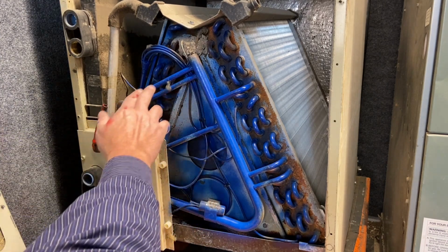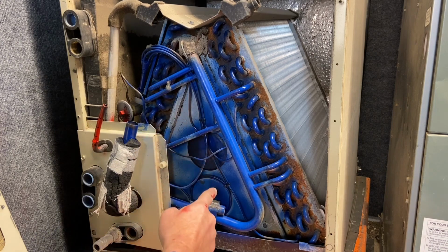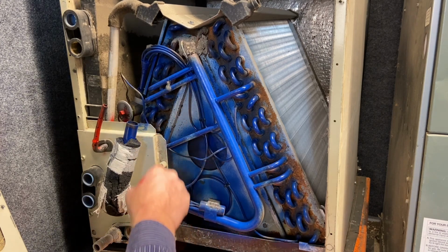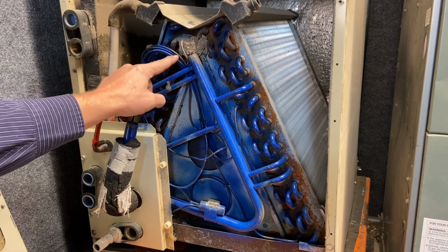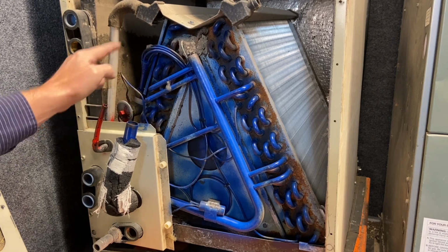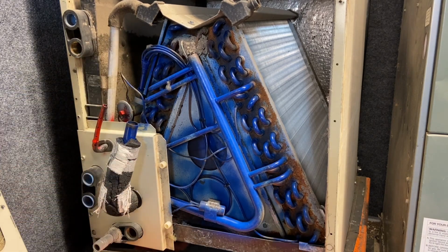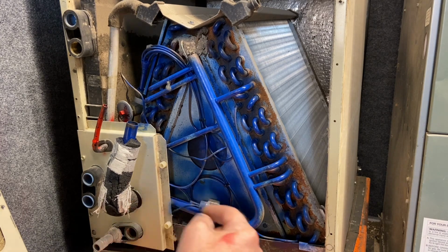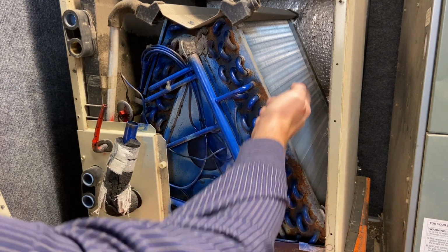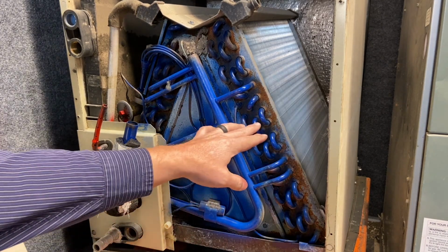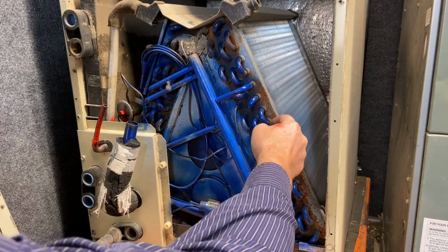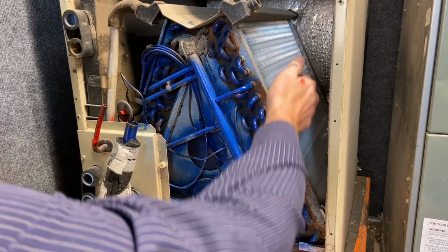And if you see, we're feeding this coil through 6 different locations. 1, 2, 3, 4, 5, 6. There's actually 6 of these little tubes. Remember, these are distribution tubes because this is my metering device. So we're distributing that refrigerant to multiple locations of this coil. Now this refrigerant runs back and forth across this evaporator coil. And all these tubes, these are called little U-bends or U-tubes, the original U-tube, but the refrigerant's going back and forth through this evaporator coil.